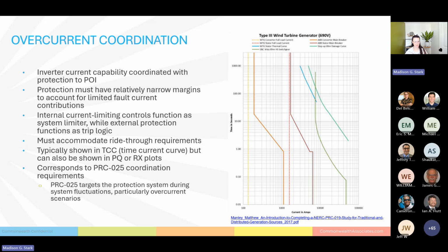Just hitting on this one more time. The current limiting controls, so this right here, which limits the current output, is really what's taking the place of those limiters that we saw on the synchronous generators. And then the external protection functions almost identically for both the synchronous and the inverter-based generation.